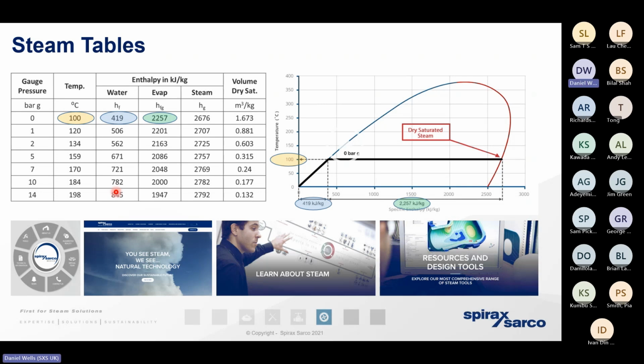Now, all of these values change as we increase the pressure of the boiler. So, for example, at 10 bar gauge, water boils at 184 degrees. You can see that we've got to have more energy in the water before it hits the boil. So that tells us that it becomes all the more important for us to recover that condensate. It tells us there's more total heat energy present within the steam, and it tells us that steam will have a smaller volume. But remember, it's the middle column. That's the useful heat energy.